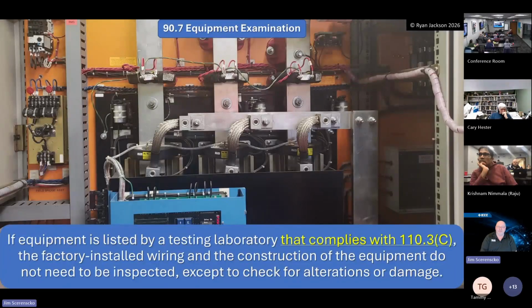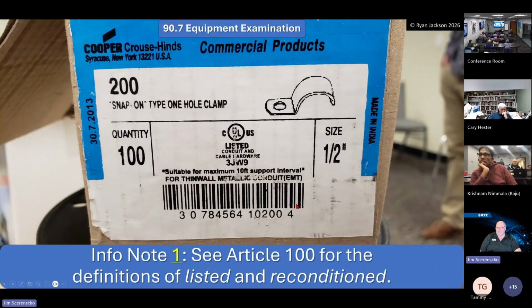That you don't have any jurisdiction inside that cabinet, okay? Other than wherever the 3 wires, if it's 3-phase, come in and land on those terminals, that's the extent of the jurisdiction we have as a municipality. Now, if I go in there and I see some metal shavings on the bottom of the cabinet and I see a new hole, yeah, I can say, hey, this was modified. I want it tested, so that you can prove to me that it still meets the standard.